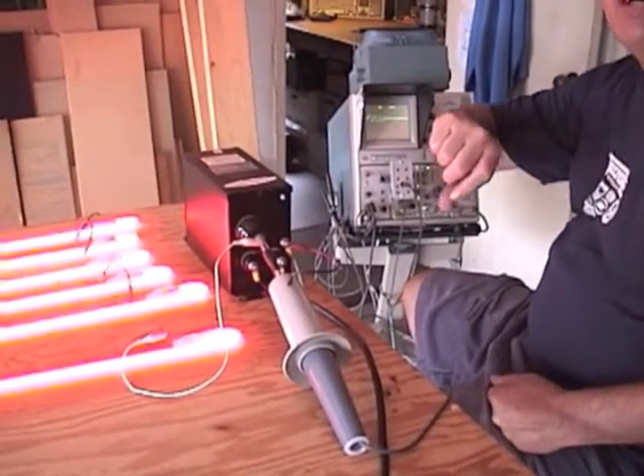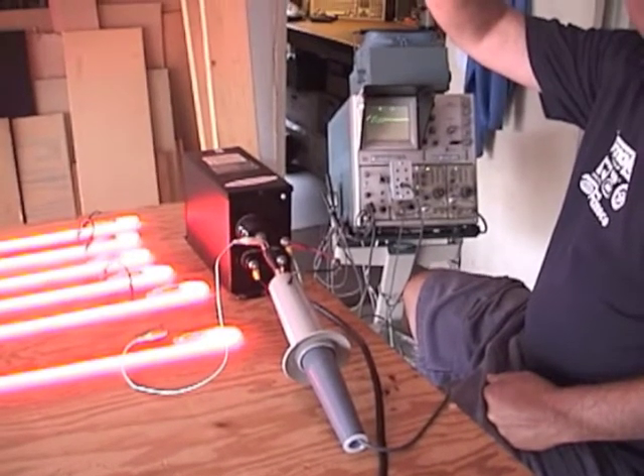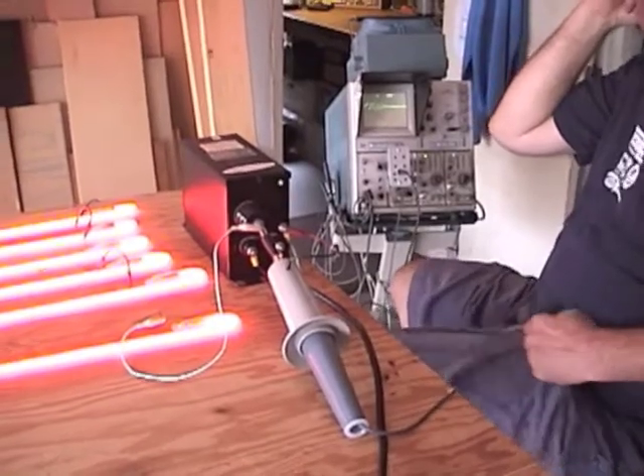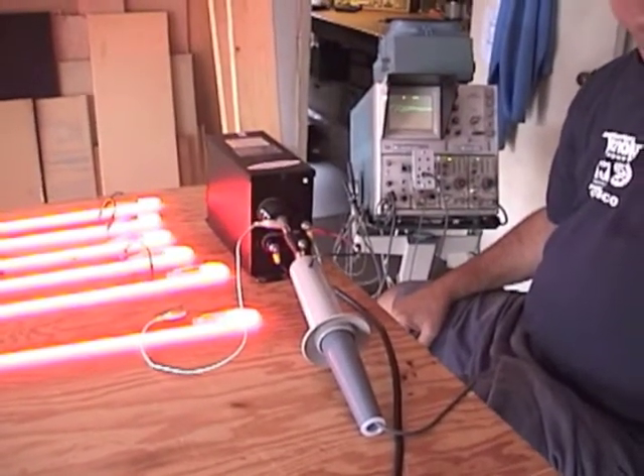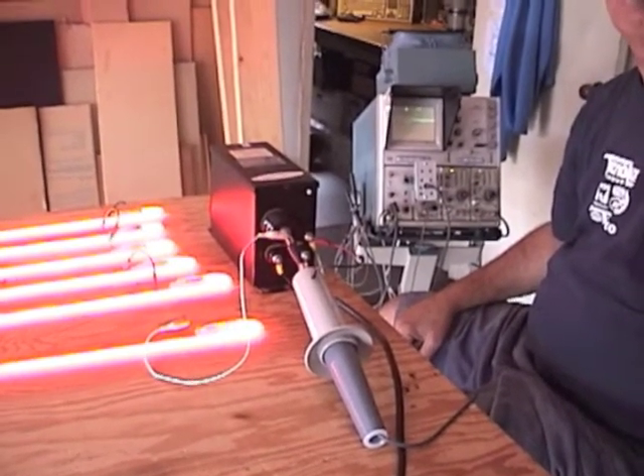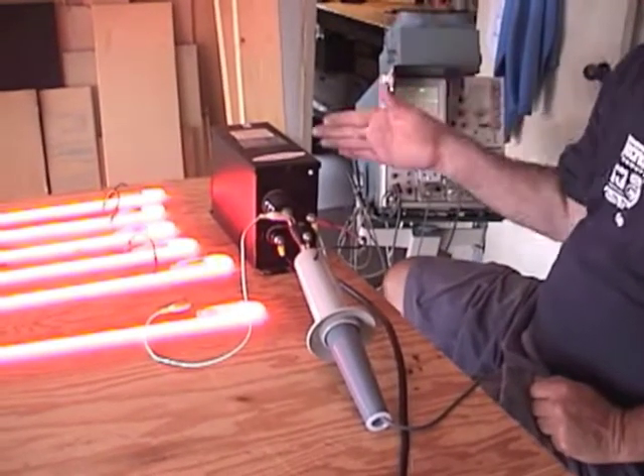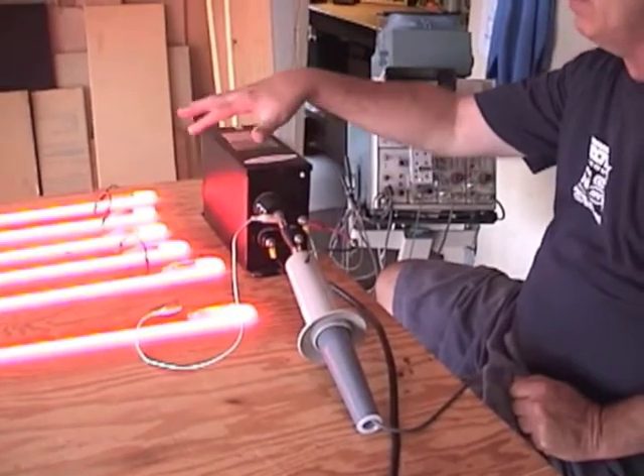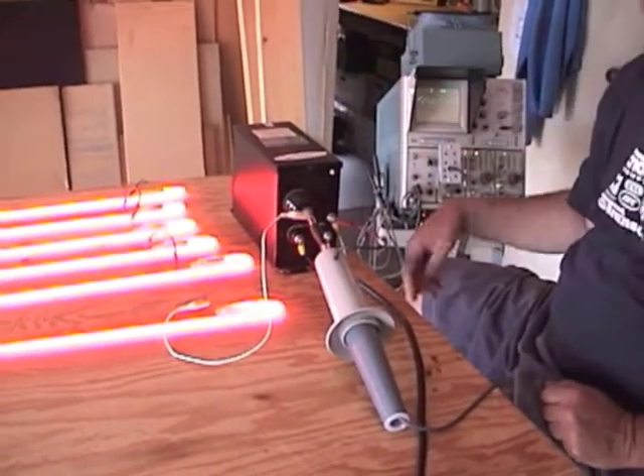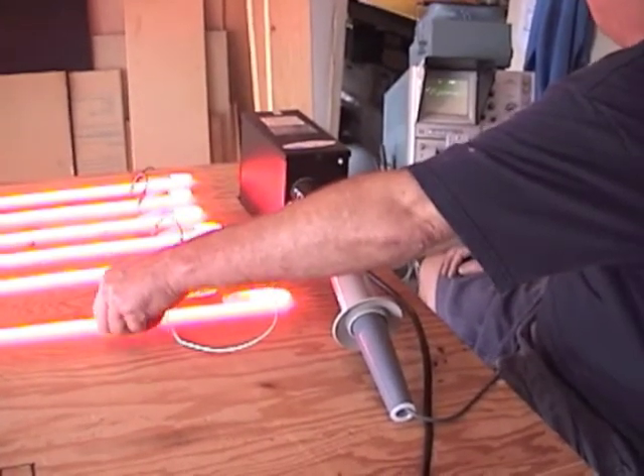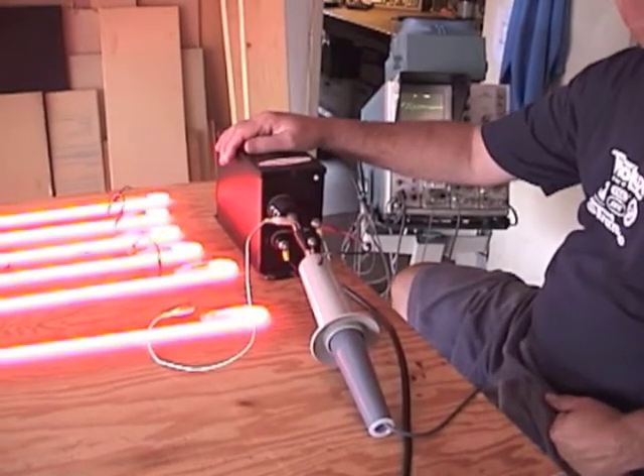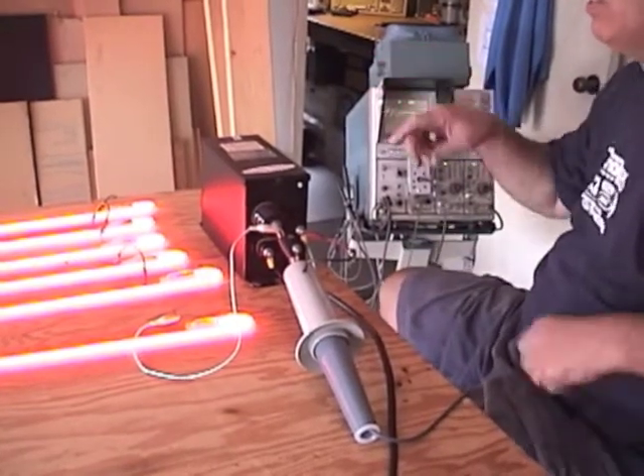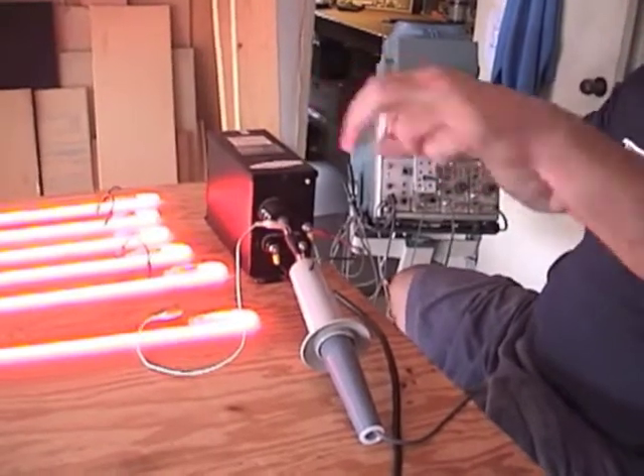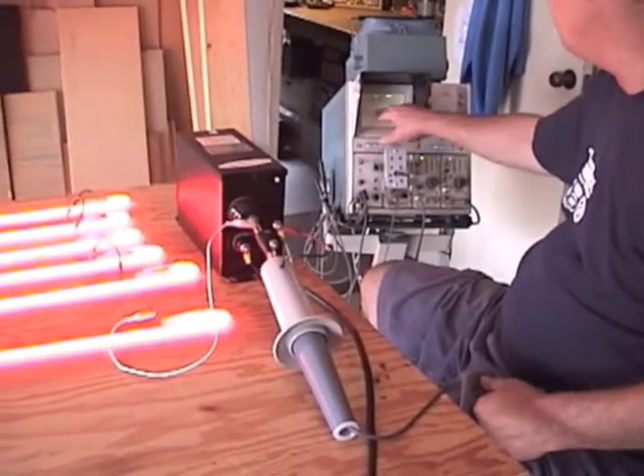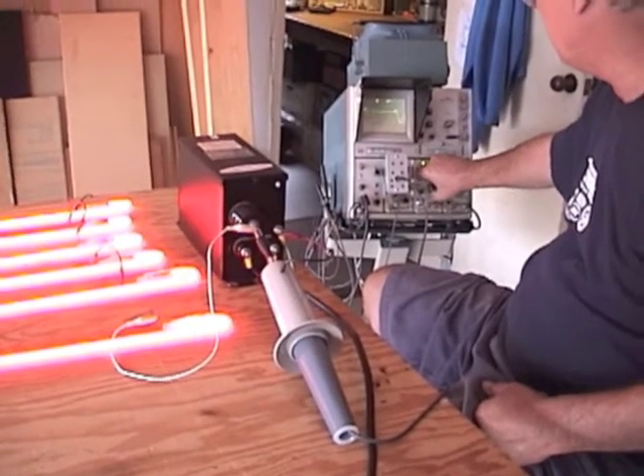What happens is the voltage out of the transformer starts coming up from zero, the tube is off, and you reach a point where the tube ignites. Neon has a characteristic that once the tube ignites, the voltage across the gas drops by a fairly significant percentage, which is a very sharp transition voltage-wise. You combine your wiring inductance, transformer inductance, and capacitance from all this glass against the table, and you form a resonant circuit. That fast drop in voltage causes all this capacitance and inductance to start circulating energy back and forth from the lamp, and it rings. So you get this ringing waveform. Eventually it dies out and you get a nice on transition like that.